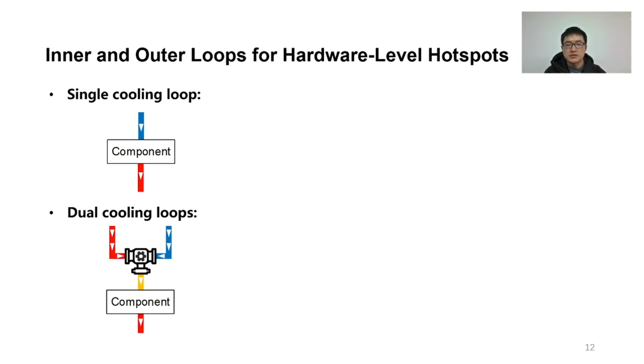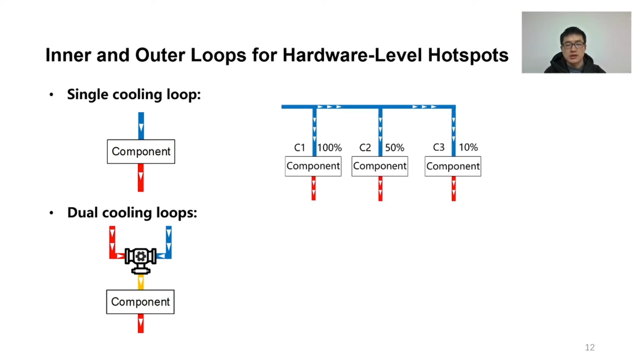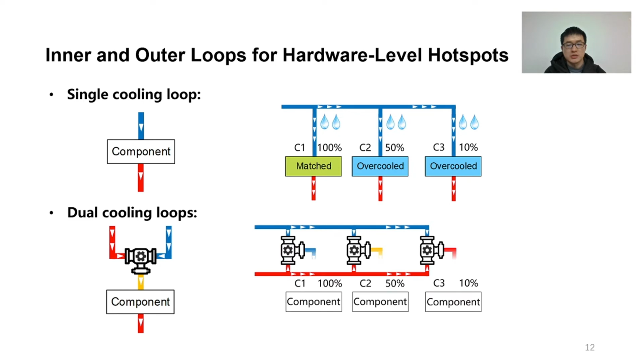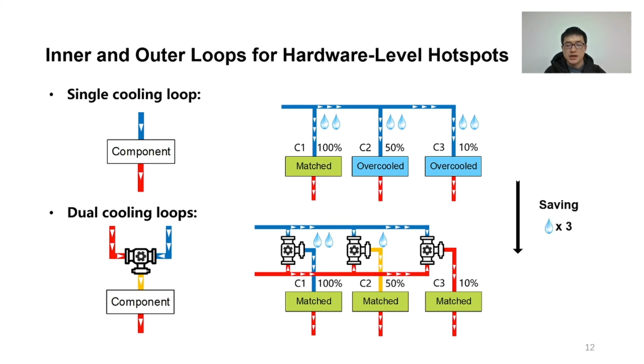Let's look at an example. Suppose there are 3 components in total, and their utilization levels are 100%, 50%, and 10% respectively. For the conventional cooling system with only one cooling loop, to ensure the safety of C1, maybe only the cold water is viable. In this case, 6 units of cold water are consumed, and C2 and C3 are overcooled. As for the proposed cooling system with 2 cooling loops, C1 is still provided with the cold water, while C2 can be provided with warm water, and C3 can even be provided with hot water. In this case, only 3 units of cold water are consumed, and all hardware components are well cooled, reducing the amount of cold water by about half.